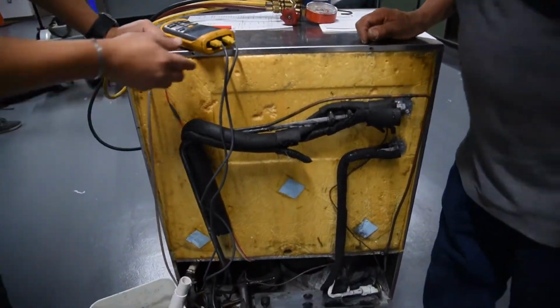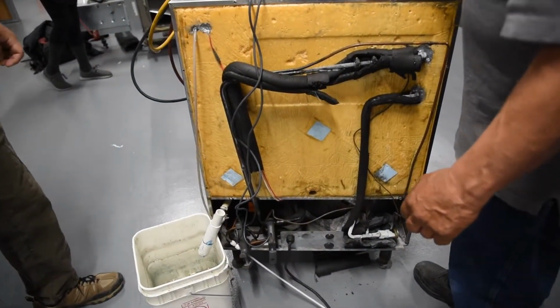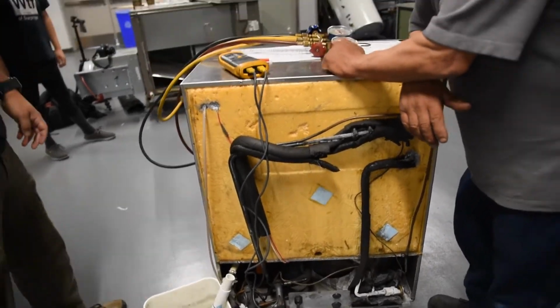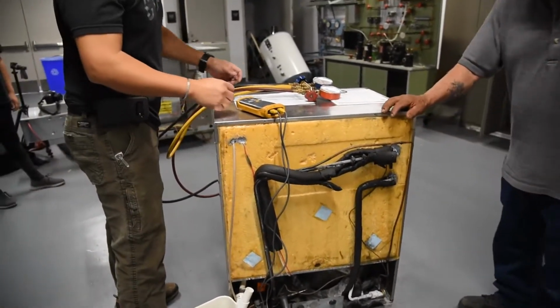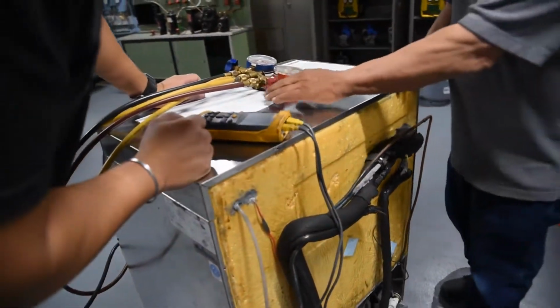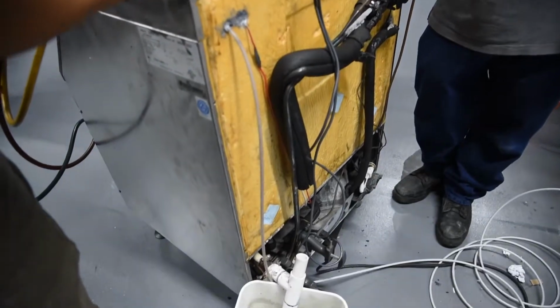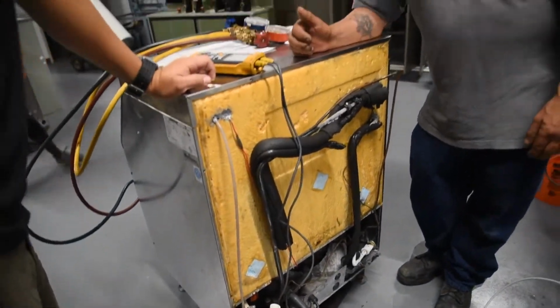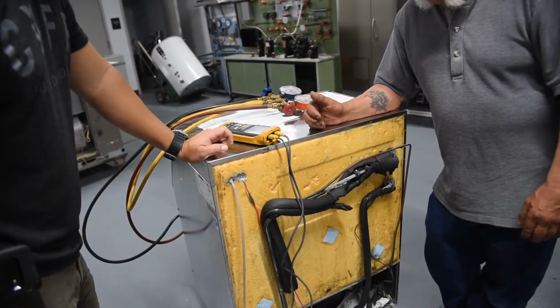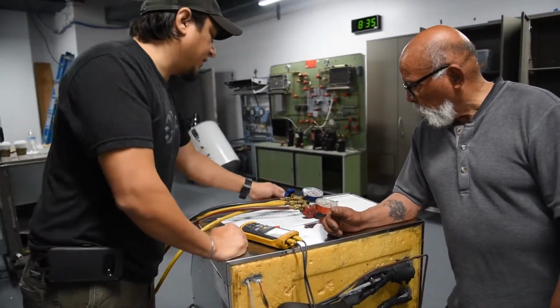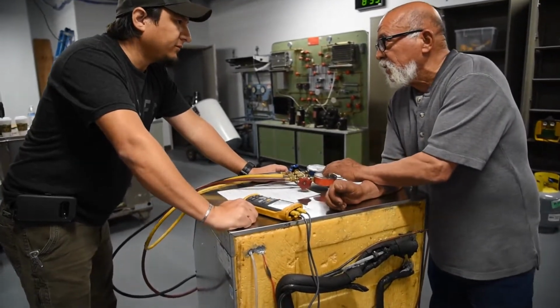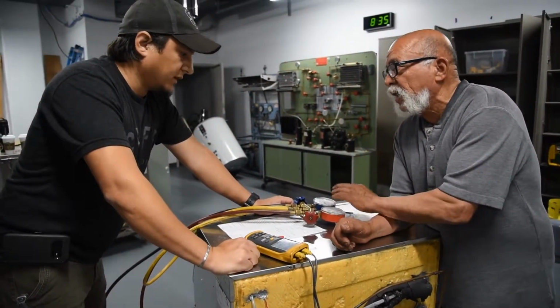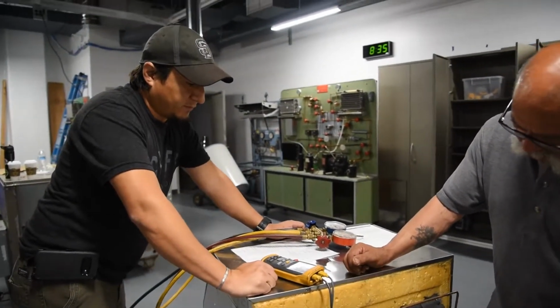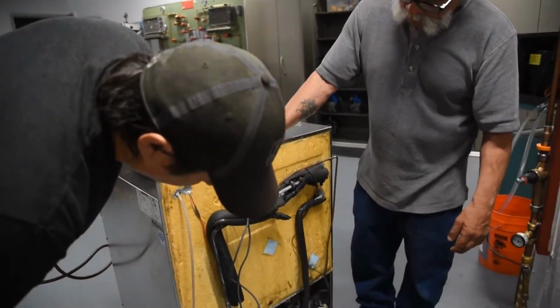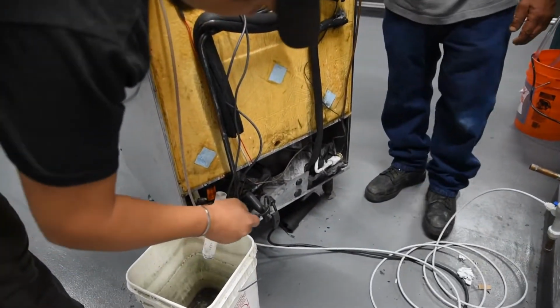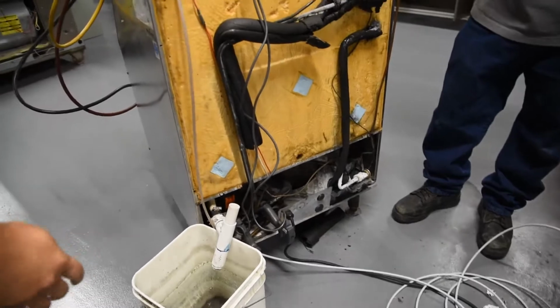So now we're going to check what the superheat and the subcooling is. How do we check superheat and subcooling? Okay, so for the superheat, we have to check the evaporator coil, the outside temperature, and we check our PT chart also. No, we don't need the PT chart. Well, that on our gauge is a PT chart, right? Oh, you mean so we know what to add, what to subtract. Correct. So what is the temperature on the liquid line? No, on the gas line, we're supposed to check for the superheat, no?